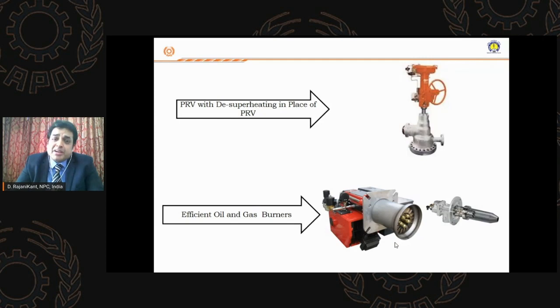The crux of any combustion is that you need to atomize the fuel. The more you atomize, the better the combustion you ensure, the more heat you get, and the combustion goes the right way. So you require efficient burners, and in the market you have very good technologies available on oil burners and gas burners, where you can ensure proper combustion.